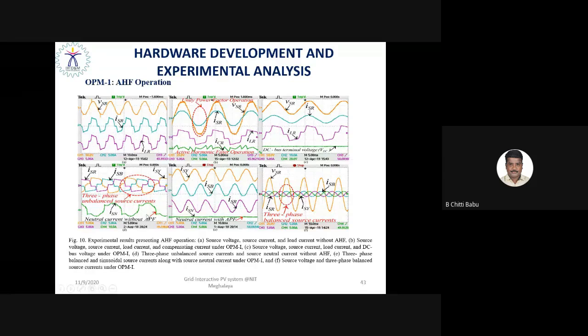As you might be knowing, the neutral current is basically an algebraic sum of the three-phase AC current. When it is balanced, there is no neutral current. When it is unbalanced, ultimately the current flows. So that current has to be neutralized to avoid overheating of the neutral wire. We propose the fourth leg. The fourth leg takes care of the neutral current circulation, neutral current suppression. So the neutral current becomes zero on the grid, and moreover the three-phase AC current becomes sinusoidal, right? So throughout the cases, you can see that the three-phase AC current is in phase with the three-phase AC voltage, and ultimately the power factor becomes unity.